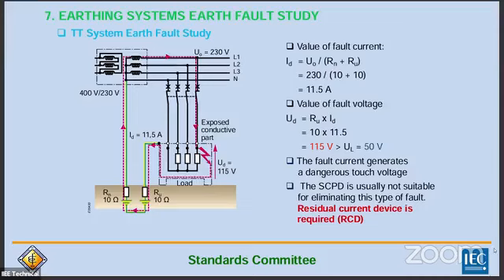So ano yung fault voltage mo dun sa body, yung exposed conductive part? This will be yung RU na nakalculate times the current, nakalculate sa ID, differential ang tawag dyan. So 10 times 11.5, 115 volts. So yun yung exposure mo, which is greater than the requirements na 50 volts.